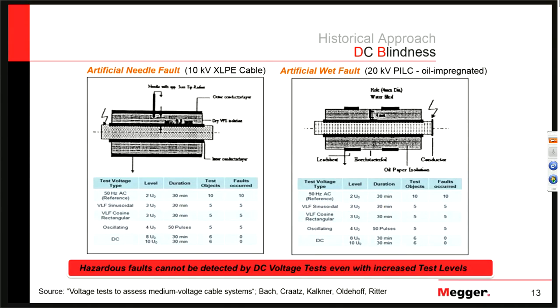VLF is much more effective at finding these faults at much lower voltages. This was true for both extruded cables and PILC cables. For PILC cables, they drilled a hole and filled it with water — same ultimate result: DC was 0%, AC was 100%.